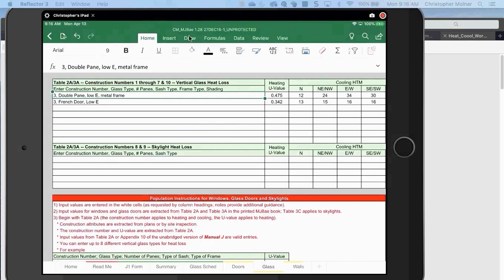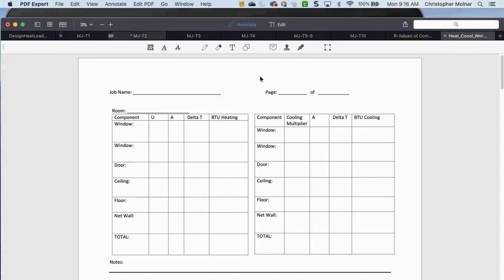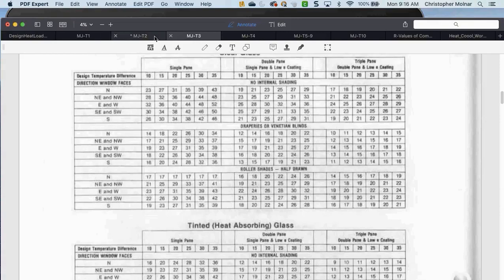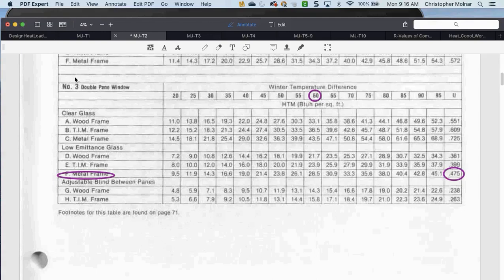Then you go to your tables 2A and 3A — T3 and T2 — that I've given you. You would find, for example, a number three double-pane metal frame window, and you find the U value for that. You could also use the BTUs per square foot, but remember what you have to do for that. Use the U value — don't back into the formula.